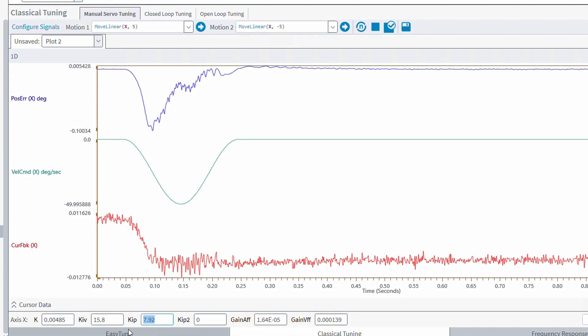Then lastly on our list of tuning tools is the frequency response tool. This is going to be the replacement for A3200's loop transmission tool. And you would come to use this if you wanted a more in-depth look at the plant response of your system, or you wanted to make fine adjustments to the tuning, or if you just wanted to add or modify digital filters in the servo loop to eliminate some kind of resonance in the system.